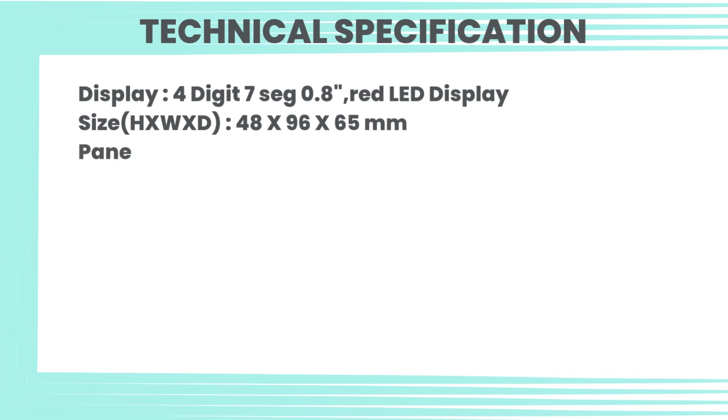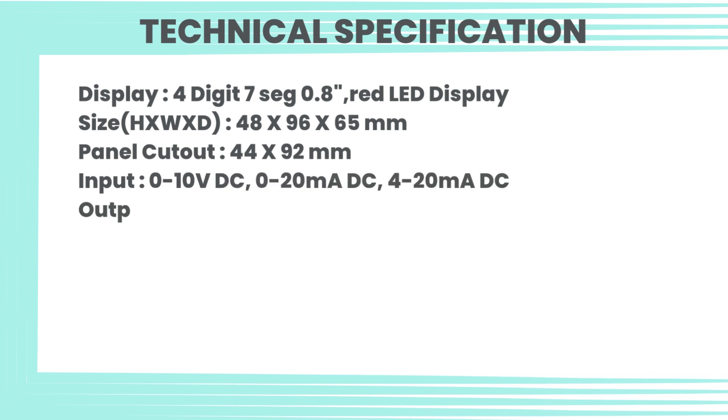Technical specification: display four digit seven segment 0.8 inch red LED display, size 48 by 96 by 65 millimeters, panel cutout 44 by 92 millimeters, input 0 to 10 volt DC, 0 to 20 milliampere DC, 4 to 20 milliampere DC.